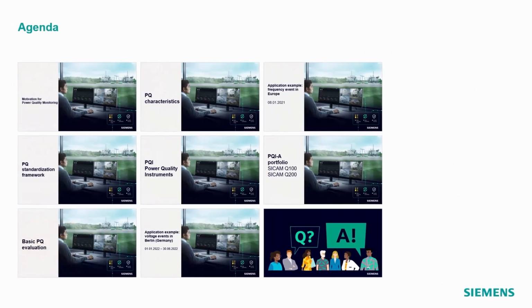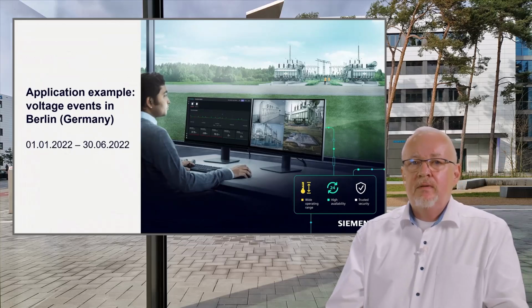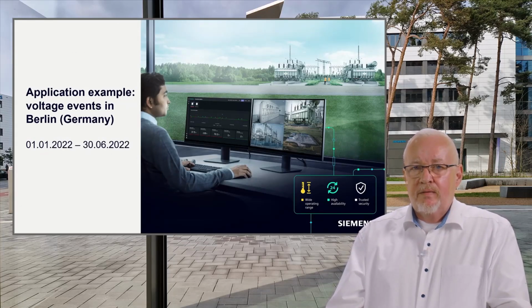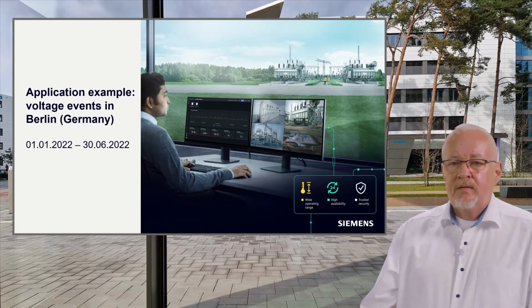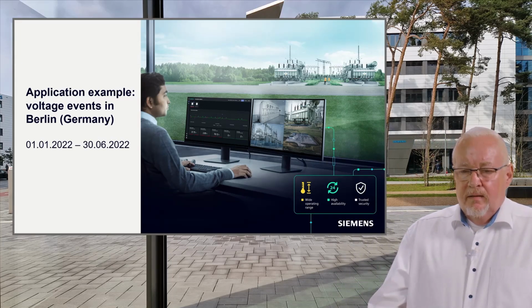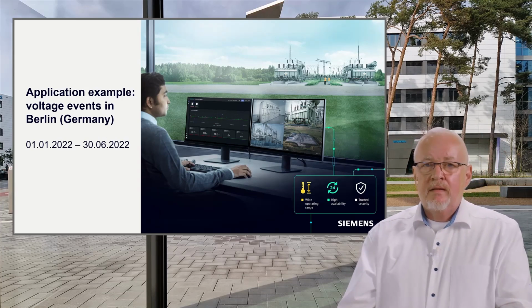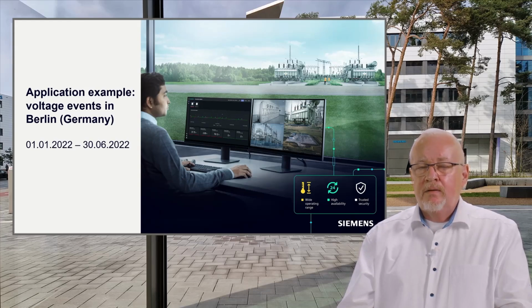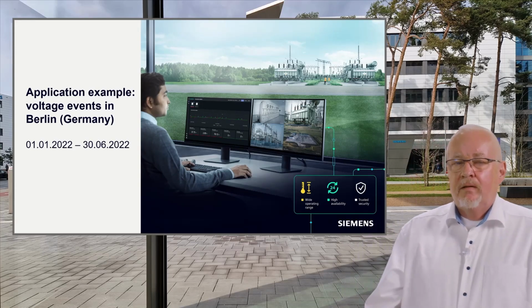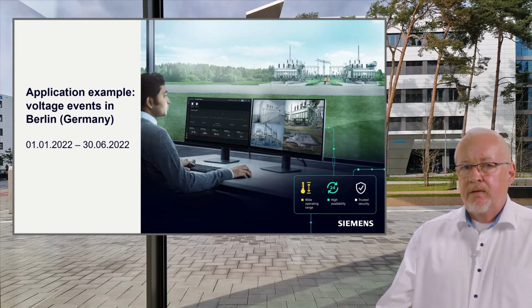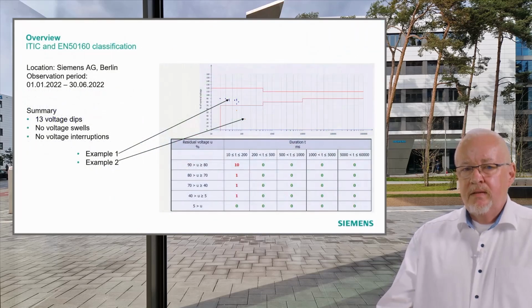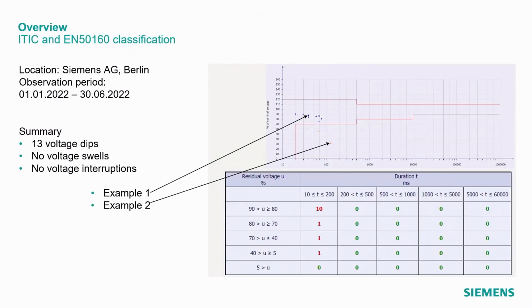Yes, okay. Then let's go to the last block of my presentation. I would give you an application example. There was a question last summer, are there voltage dips observed in Germany? And so different measurement locations were invited to analyze their events in the grid. And I took part in this evaluation, and I checked my devices in Berlin. There are a lot of devices installed in the observation period from 1st of January 22 to 30th of June 22. And what happens within that time? There's an overview here, the location, Siemens AG in Germany, Berlin, Germany, observation period. I also mentioned it. And the summary is 13 voltage dips occurred, no voltage swells, and no voltage interruptions.